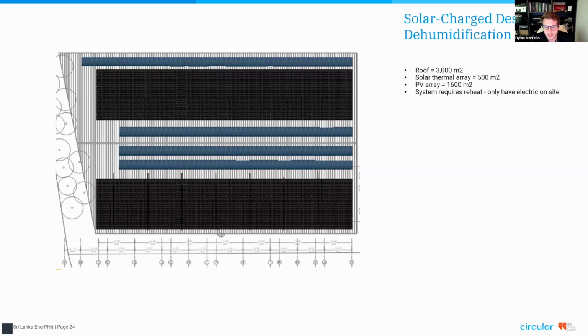What we determined at this stage was that not only is this system novel and unique, and may add some complications to the project, it also was likely going to result in a high energy load because it's really a solar assisted desiccant-based dehumidification system. We would have had to rely on electric water heaters to bring the water up to an adequate temperature to make this desiccant evaporative cooling process happen, and that temperature needed to be about 180 degrees Fahrenheit, about 82 degrees Celsius—you needed really hot water. We were concerned that might end up resulting in a lot of energy use as is. Next slide.